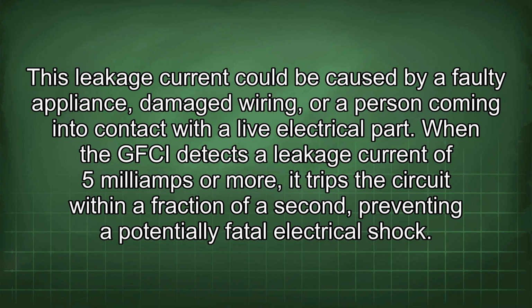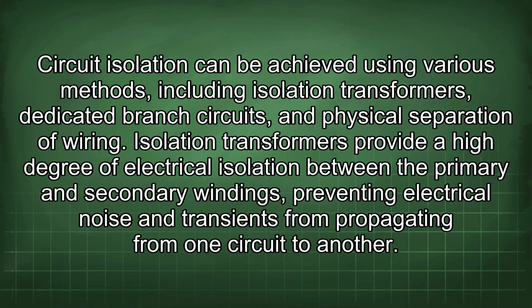When the GFCI detects a leakage current of 5 mA or more, it trips the circuit within a fraction of a second, preventing a potentially fatal electrical shock. Circuit isolation can be achieved using various methods, including isolation transformers, dedicated branch circuits, and physical separation of wiring. Isolation transformers provide a high degree of electrical isolation between the primary and secondary windings, preventing electrical noise and transients from propagating from one circuit to another.